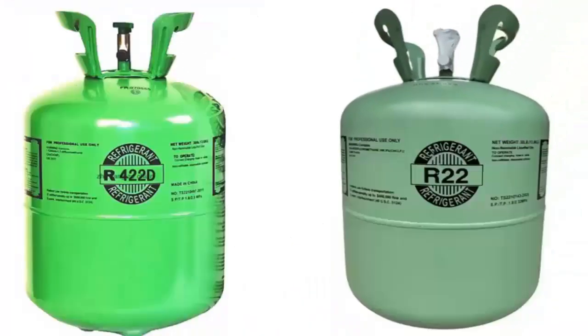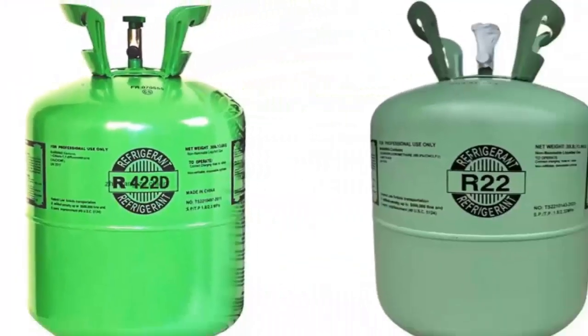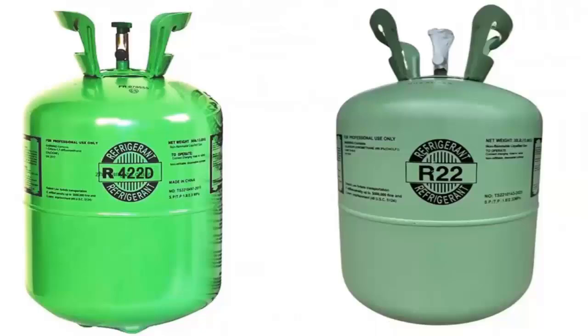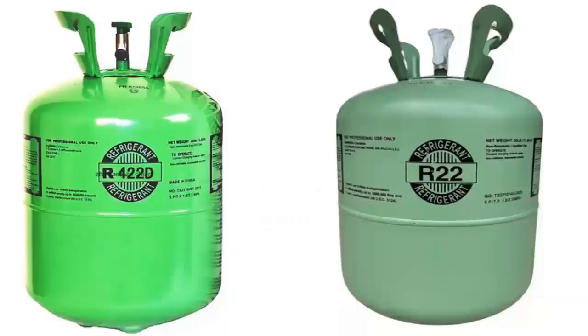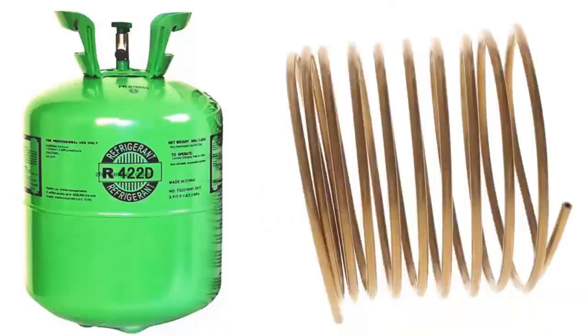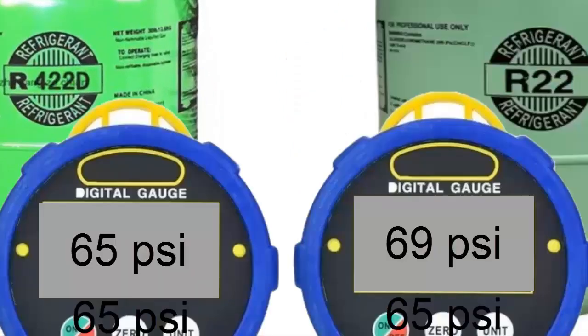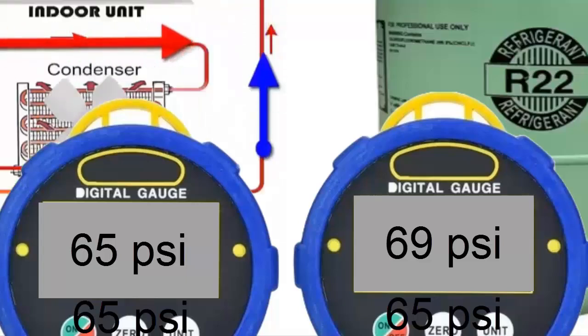C. R422d. This replacement gas for R22 does not require changing the compressor oil. The recharge must be done in the liquid phase, and the original R22 capillary tube should be used. On screen, we compare the working pressures of both refrigerant gases.